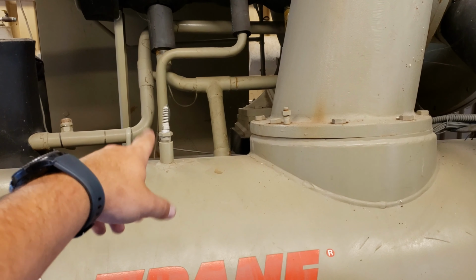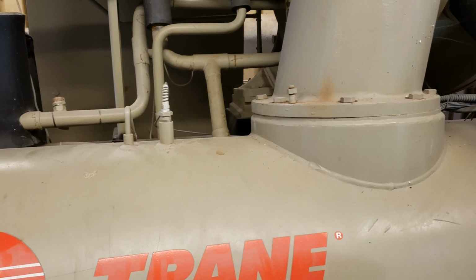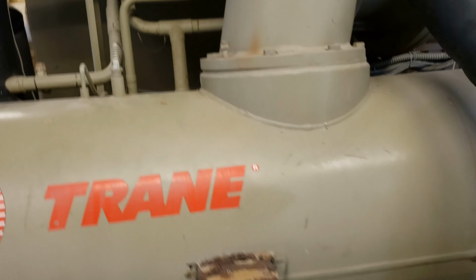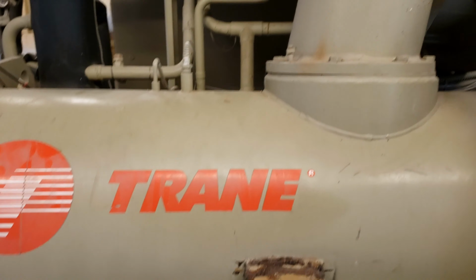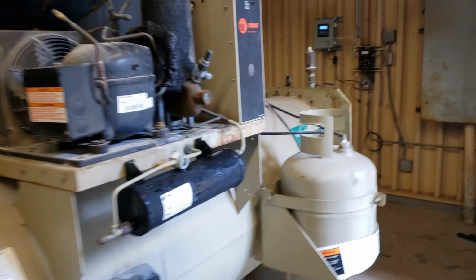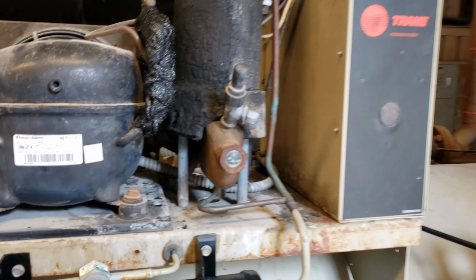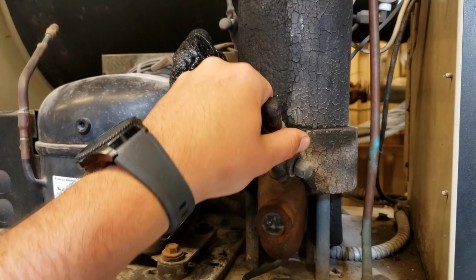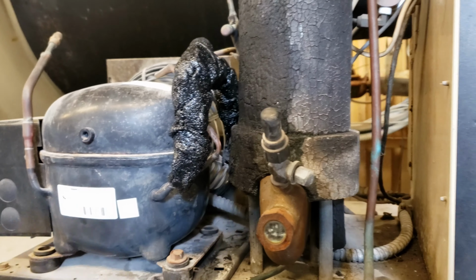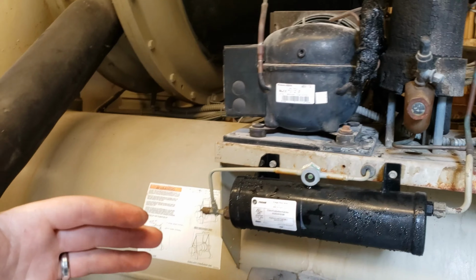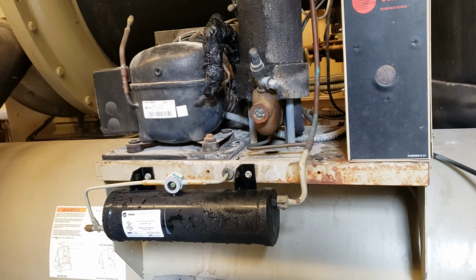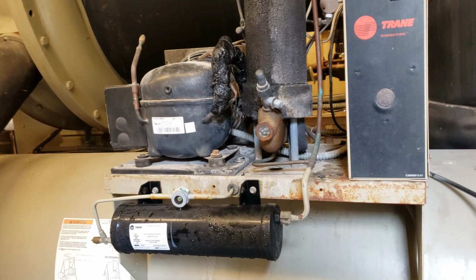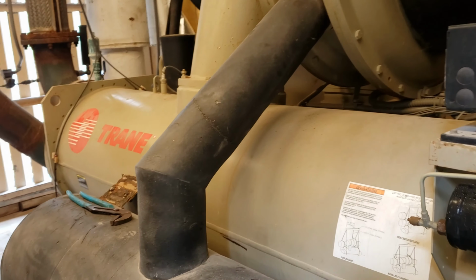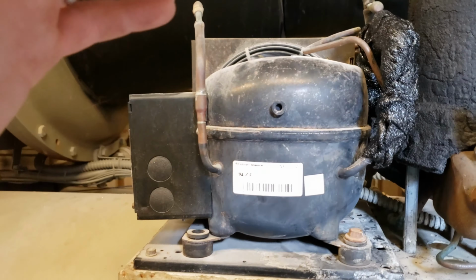What it came down to was, I spoke about that discharge sensor. It was out of range. It was reading about 15 degrees off. Got that changed, and that really helped our purge assembly in finding that temperature, and it worked up to a certain point, but the purge only purged so much. I could tell by my readings I still had a lot of atmosphere in there, but the purge just wasn't seeing it. And so it really made me start to question the suction sensor on the purge.